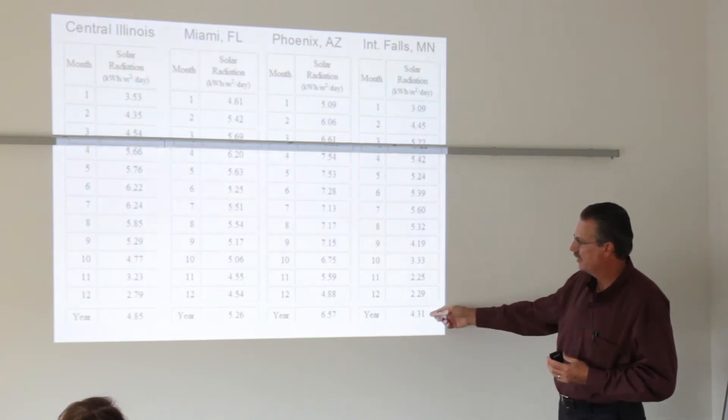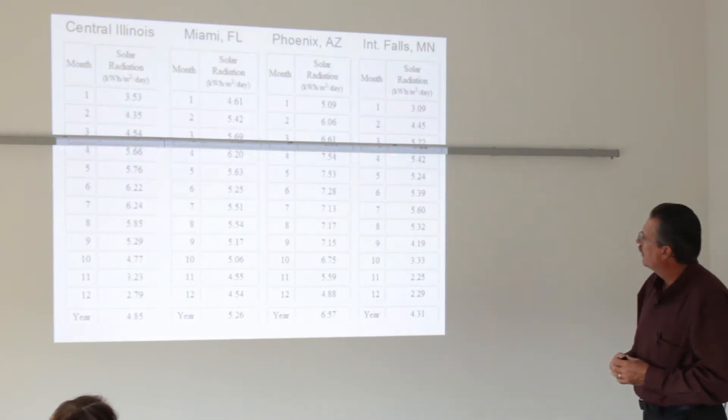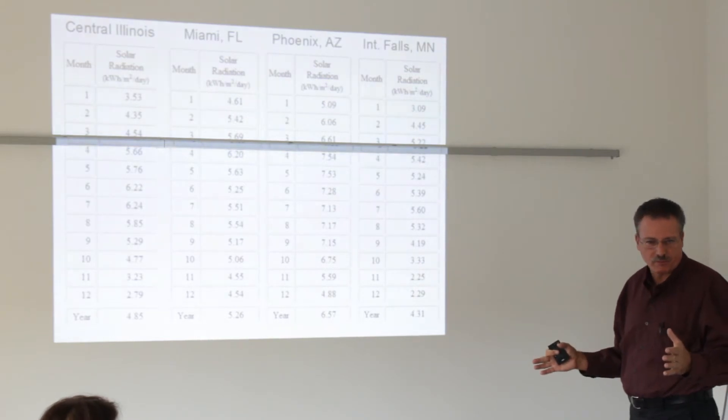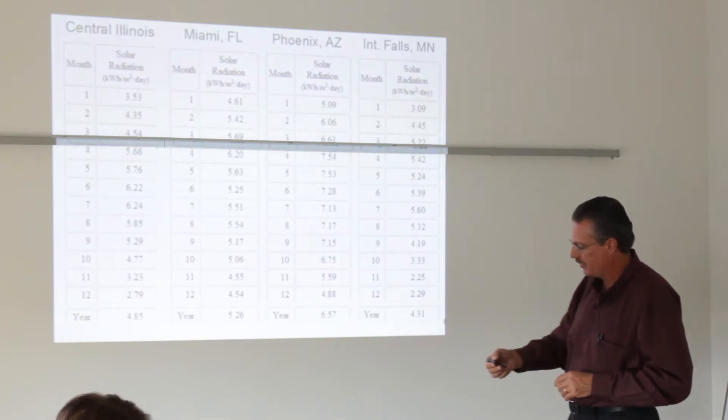International Falls, Minnesota, 4.31 compared to 4.85 for central Illinois. It's still very viable and you don't write it off. You just say we're not going to get as much energy per square meter so we're going to increase the size of the array to make up for a little less resource. So it works out quite well.